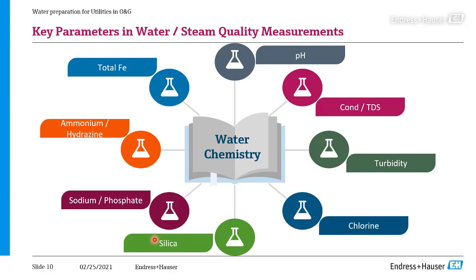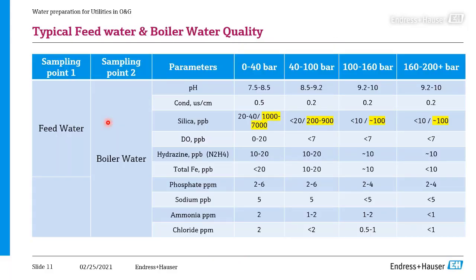Then silica as a deposit has to be removed from the water, as well as sodium, and hydrazine is used for the deaeration to keep oxygen at a low level, and total iron. So these are some parameters which help us to control the processes. And on this table, you see some of the criteria.